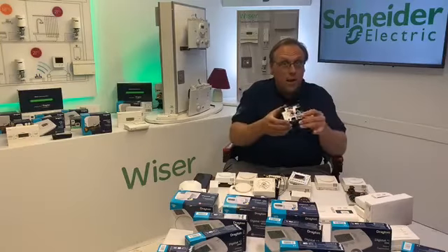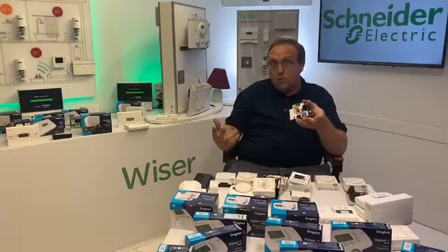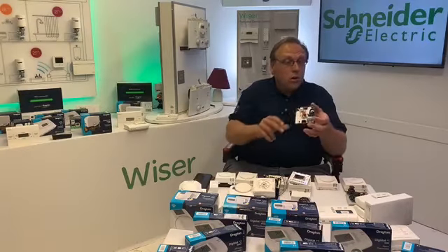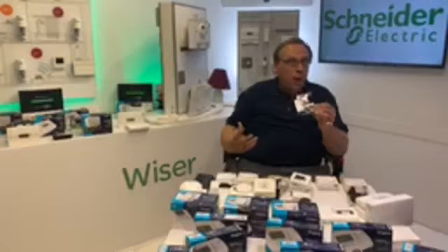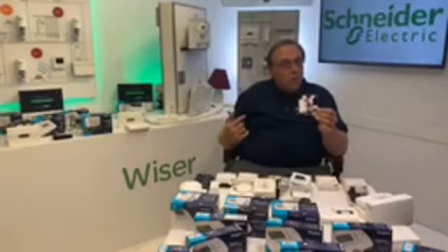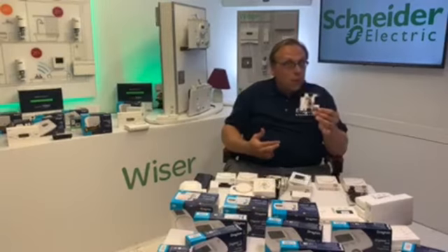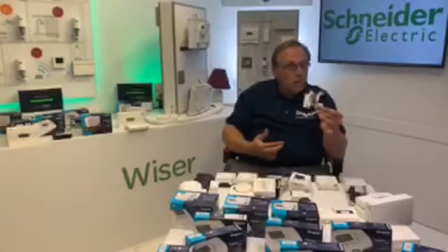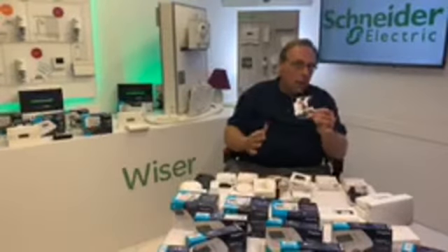And the reason I say that is it works as a 3-wire thermostat. So if you've got a neutral, a live in, and a switched live out, you can wire it as a 3-wire thermostat. But if you've got just a live in and a live out, so a 2-wire thermostat, you can use this in its place. So you don't need a neutral necessarily to run this. You can if you've got it. If you haven't, it doesn't make any odds.